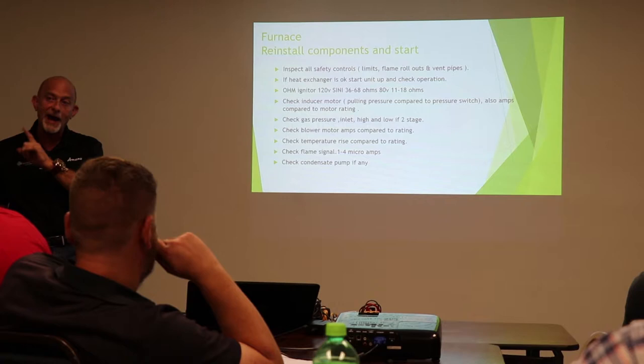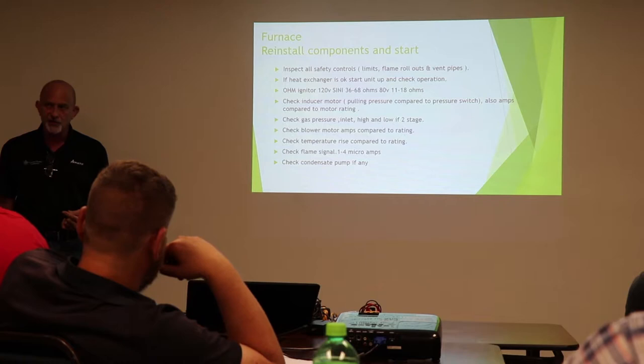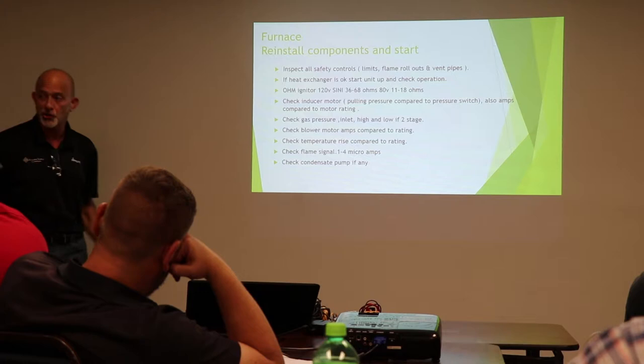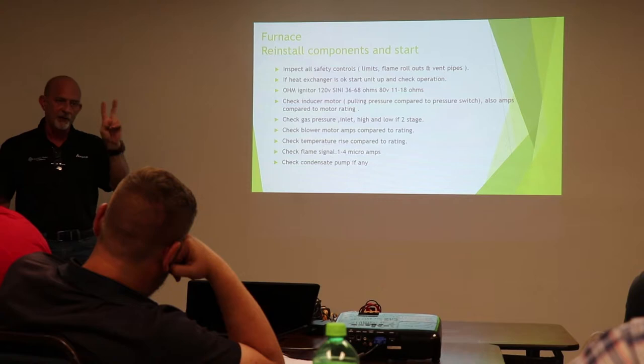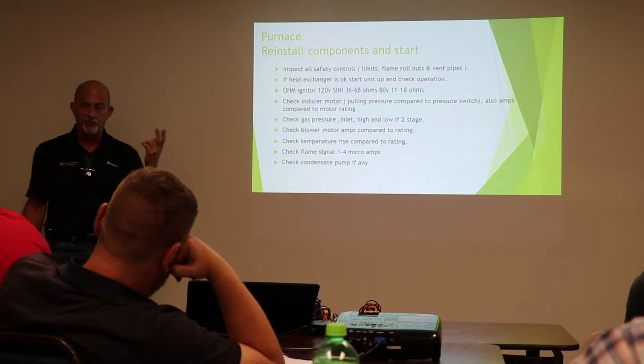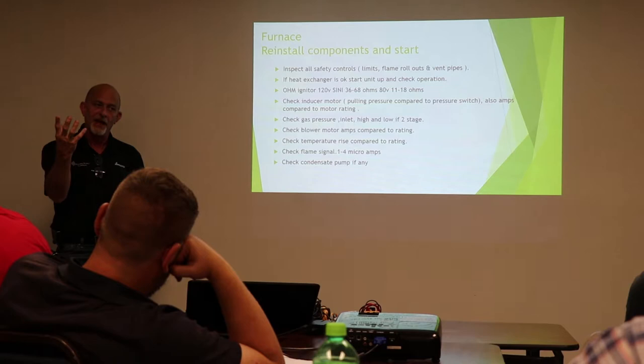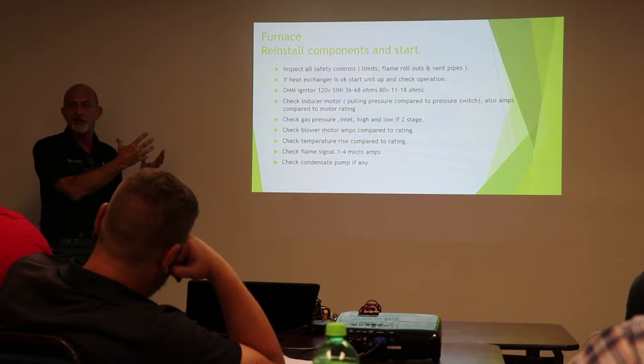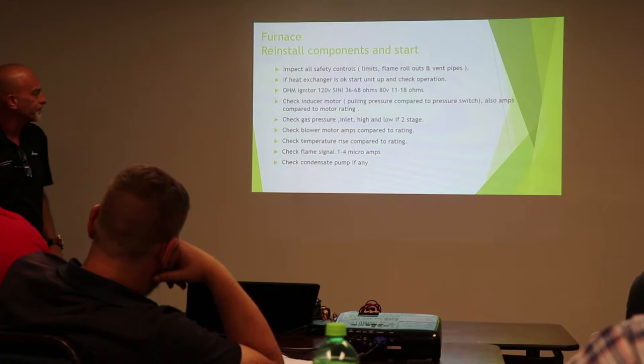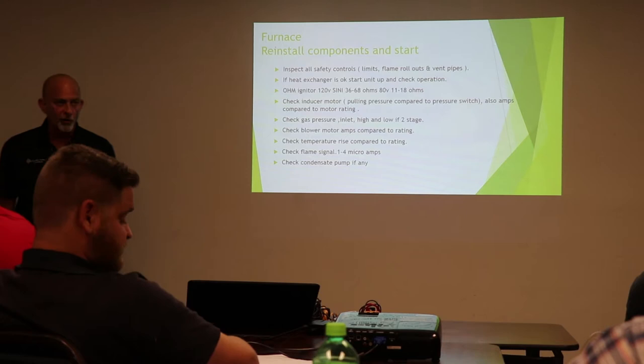If you have a condensing furnace with a sealed combustion, we are bringing air from the outside. Now, for a two-pipe system, we can have a blockage in our intake pipe, not getting enough oxygen for flame, and the flame is searching for oxygen, so it'll pull back trying to get the oxygen it needs to burn and trip the flame rollout. So you may not have a bad heat exchanger. Could have a hornet's nest in there. You could have a squirrel. I ran into a rabbit. A squirrel. A mud dauber. In there? Mm-hmm.